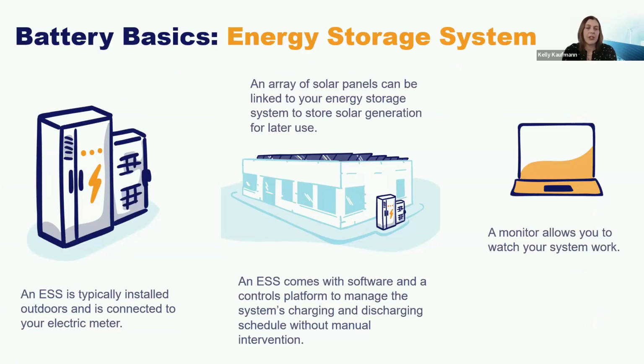First consideration is the location for the battery, and this comes up a lot with our customers. It's recommended that energy storage be sited in an outdoor location whenever possible, offset from the building by several feet. If you have an area where other large equipment is located outside your building, that might be a good place to look first. Customers have often considered leveraging a portion of the parking lot or pouring a new concrete pad on the exterior of the building to house the system.